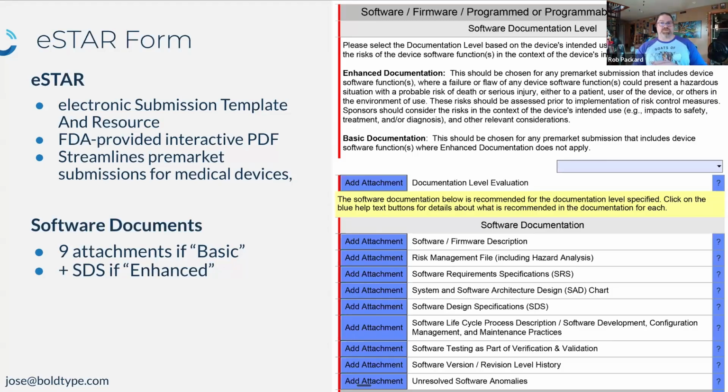And if you read ISO 13485:2016, it doesn't say anything about design of software. It talks about validation of quality system software. It talks about validation of calibration software. It talks about equipment like sterilizers, that equipment being automated, and validating that. It does not talk about 62304 other than, go see 62304. So there's no updated one.